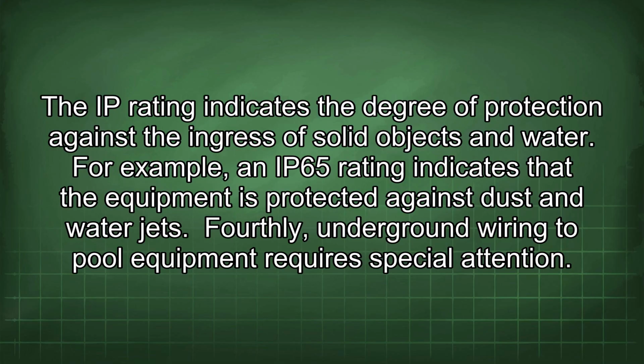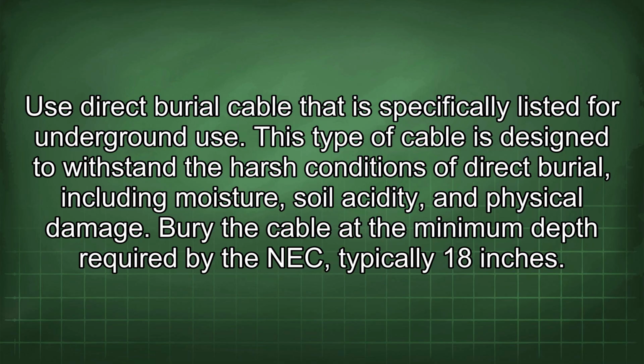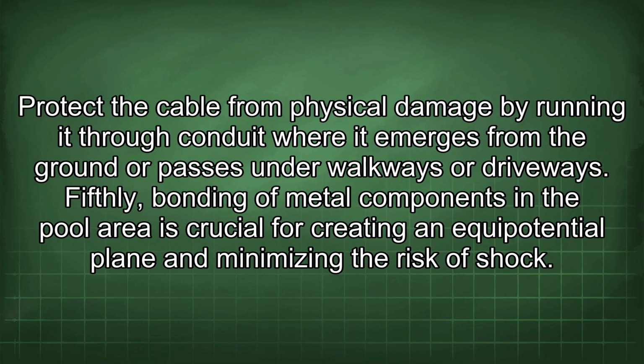Fourthly, underground wiring to pool equipment requires special attention. Use direct burial cable that is specifically listed for underground use. This type of cable is designed to withstand the harsh conditions of direct burial, including moisture, soil acidity, and physical damage. Bury the cable at the minimum depth required by the NEC, typically 18 inches. Protect the cable from physical damage by running it through conduit where it emerges from the ground or passes under walkways or driveways. Fifthly, bonding of metal components in the pool area is crucial for creating an equipotential plane and minimizing the risk of shock.